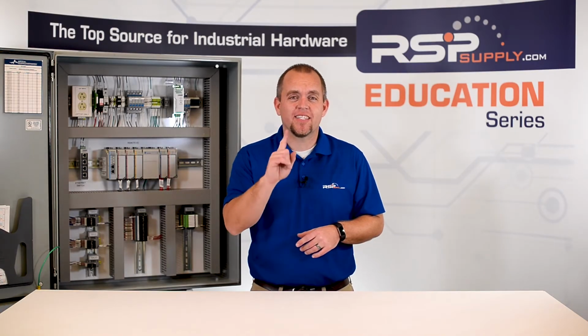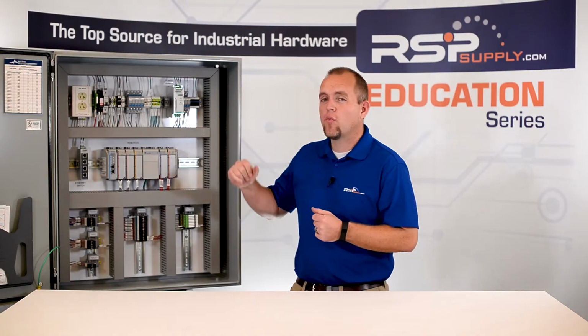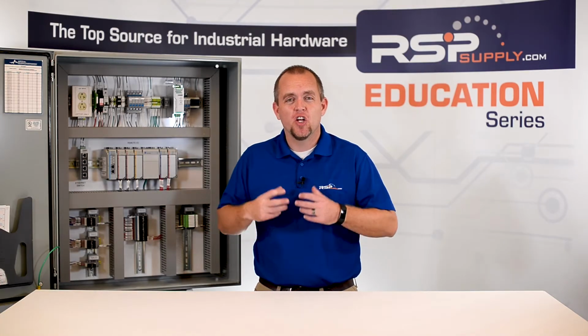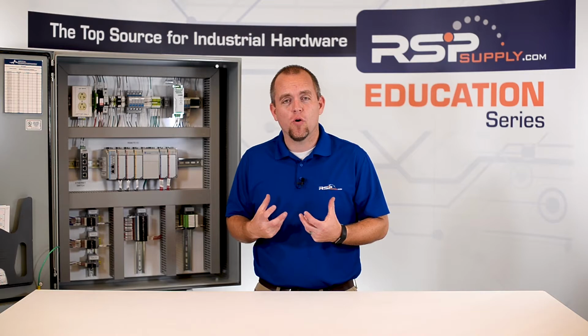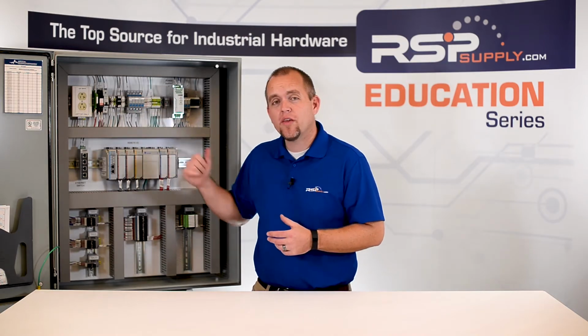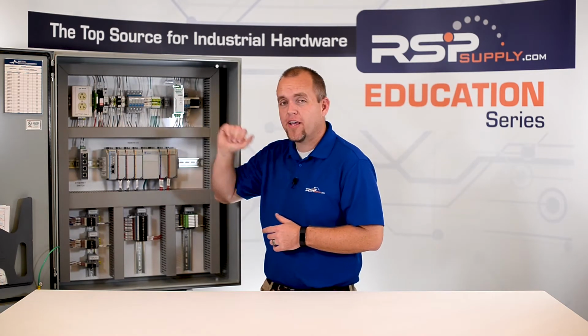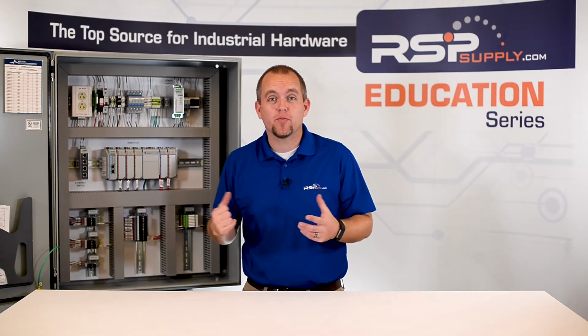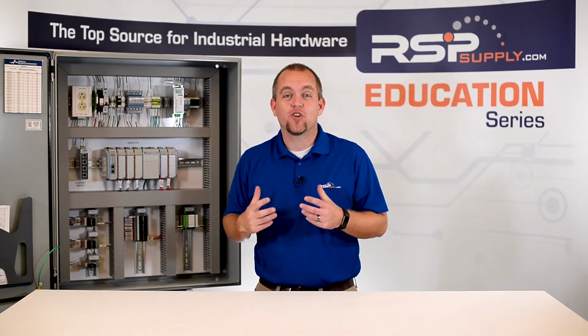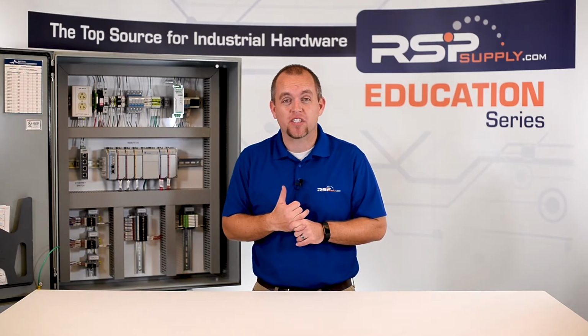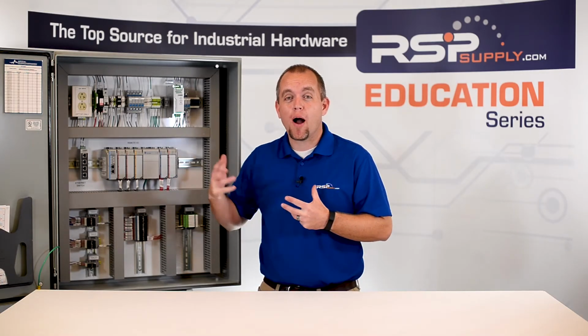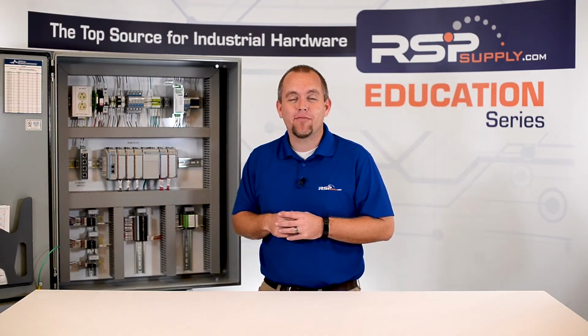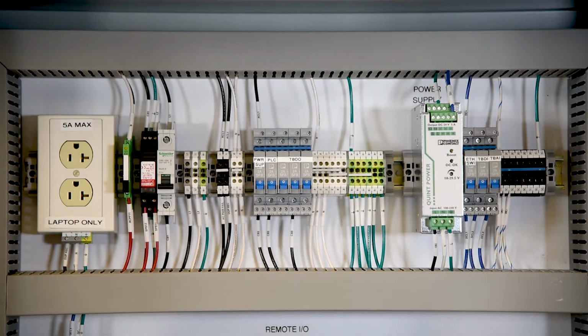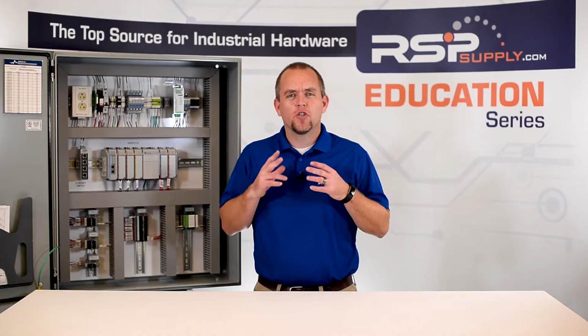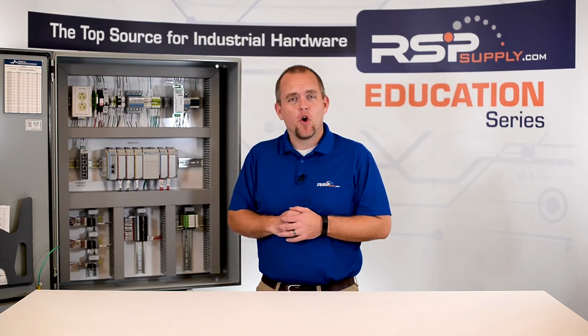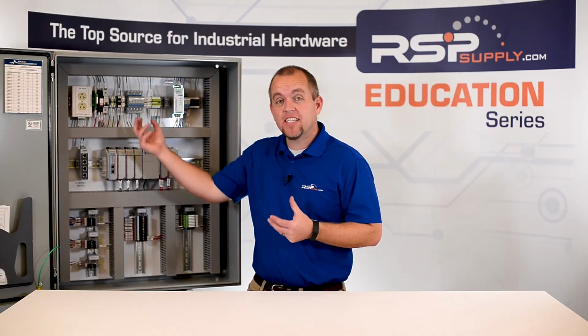Number one is safety. It is very important when we are talking about power distribution to know what kind of power, first and foremost, that we're dealing with. Do we have 120 volts coming into our panel, like this panel here, or do we have 480 three phase power coming into our panel? We need to make sure that we properly identify the power that is coming into our panel so that people who are operating within the panel can easily identify and make sure that they are prepared to operate and use this panel. So again, in the case of the panel we have here today, we have 120 volts that are going to be coming into this panel.